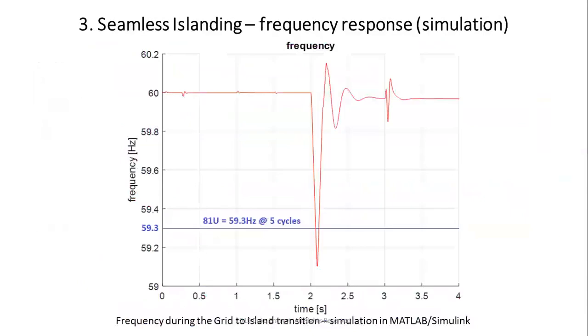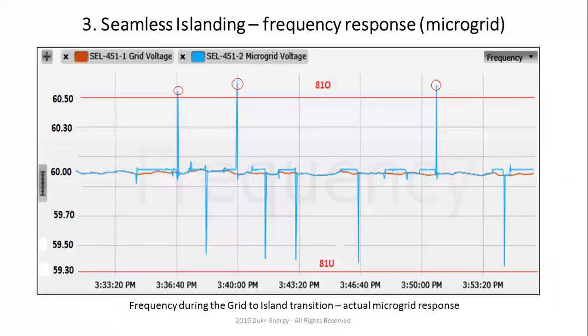Okay, so now look what happens to the frequency, right? Frequency response: our settings are 60.5 and 59.3 at 5 cycles. And during the transition, this is what happens. Let me tell you what happens essentially during the transition. The transition, from the moment that we initiate islanding till the moment that the islanding is over, is 128 milliseconds. Our battery energy storage system has an inverter that operates in VSI PQ mode when it's connected to the grid, even though you can operate in CSI PQ mode. This one operates in VSI PQ mode. So it actually has to switch 3 operating modes within 128 milliseconds, right? This is what happens during the operation of the microgrid with respect to the frequency settings. They go outside the normal range. So now you have to understand what happens with protection and control settings during this transition, right?